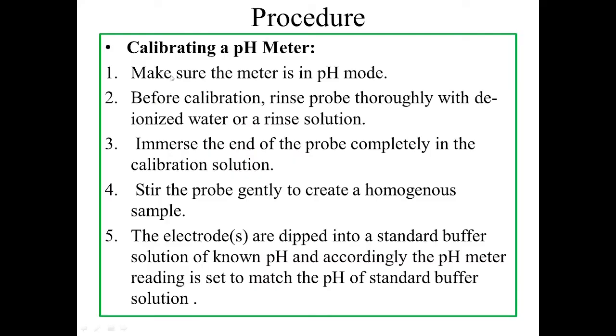Then the first thing we need to do is calibrate your pH meter. If your pH meter is kept as such without use, some changes may take place in the electrode. So the first thing we need to do is calibrate your pH meter so that accurate readings of the sample are obtained. Okay, so now make sure that the pH meter is in pH mode. Adjust the pH meter to pH mode first.